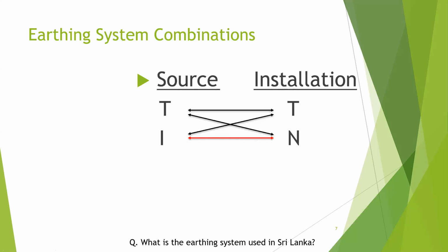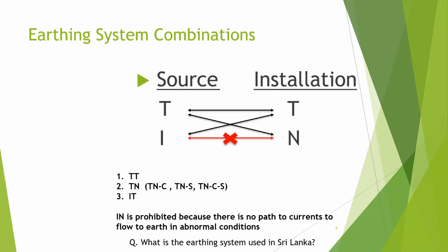Earth means the soil. So in the first system, both sides are connected to earth. In the second system, the source side is connected to earth, the installation side is not. In the third system, the source side is not connected to earth, but the installation is connected to earth. But in the fourth, the IN type, the source is not connected and the installation is also not connected. So this is not an earthing system. So we are not allowing the IN system. So we have three earthing system combinations available in earthing system installations. We have several sub-variants also.